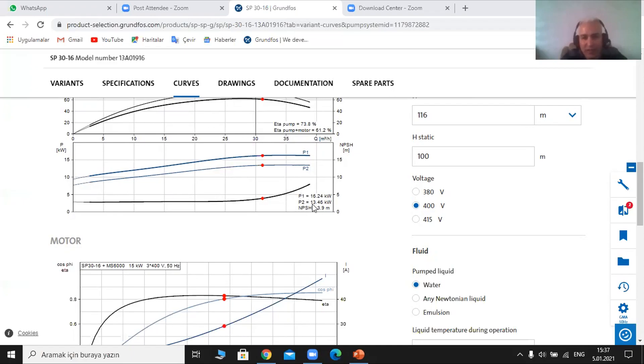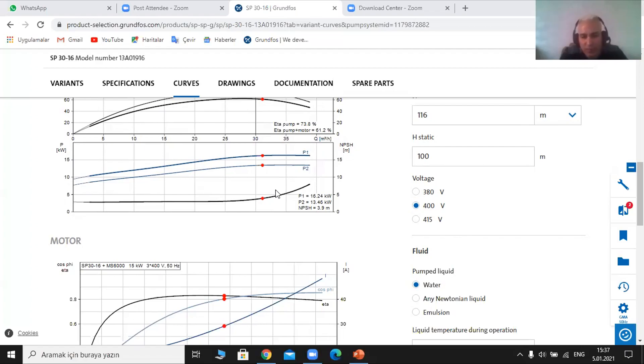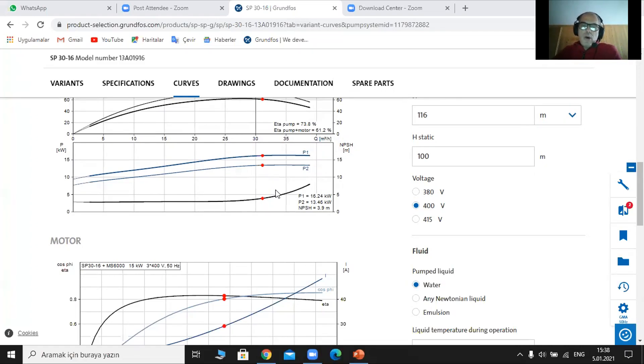P2 is the mechanical value on the pump shaft, which is 13.46 kW. The NPSH — the water level above the pump — means the depth of water at the point where, if it is less than 3.9 meters, I would have problems and issues within the pump. There is a question: the water level below the pump should be 3.9 meters, but in a borehole the water level is dynamic and will vary — so this has to be considered as well.